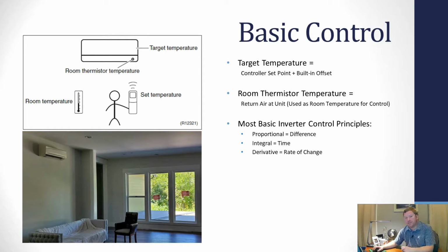So you give the unit a set point. It has a built-in offset. So let's say, for example, you give the indoor unit a 70-degree set point. The indoor unit is going to say, okay, my target temperature is 73.5. And again, depending on the unit, this offset number may vary. On some indoor models, it might only be 2.5, and on some indoor models, it might be 4.5. The typical standard is right around 3.5 degrees.